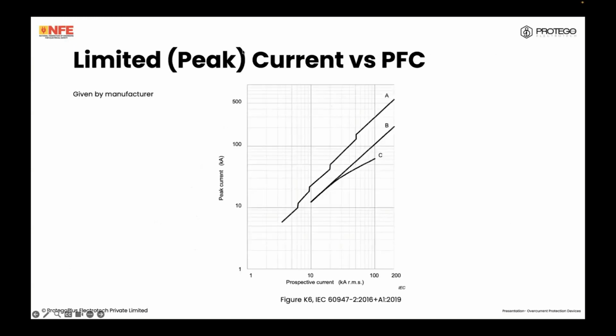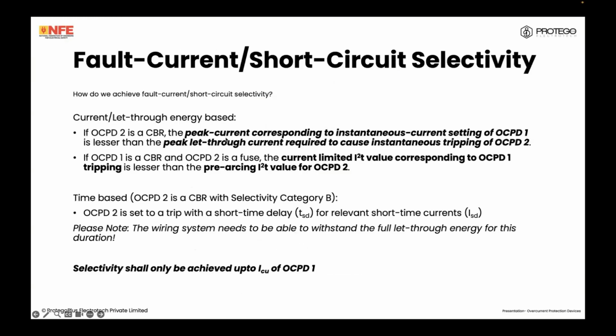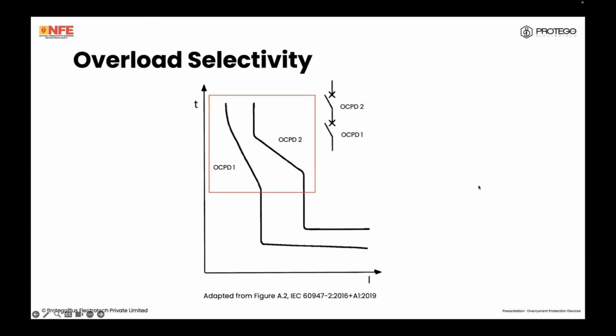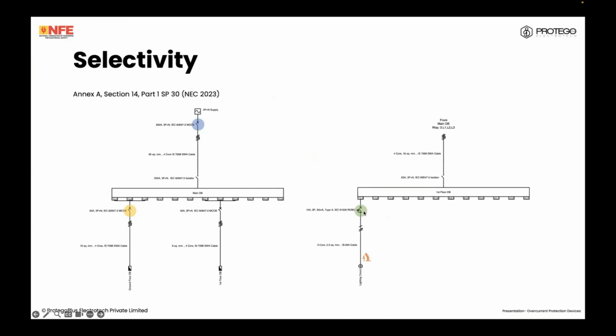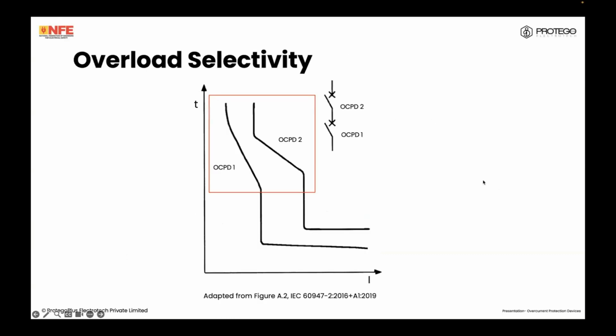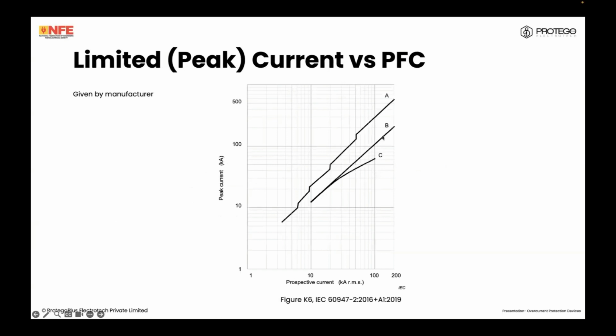Now, when it comes to this, like I said, we need to find out the peak current corresponding to the instantaneous tripping setting of OCPD1, which means when this, say, RCBO or MCB trips, what is the peak current that this circuit breaker and this wiring is going to see. This is given as a graph. Look at this B line here. The manufacturer will tell you, and they are required to tell you if they comply with 60947, that for a certain prospective current, this is the peak current that will be seen by the system. C is for a current limiting device. So keep this in mind.